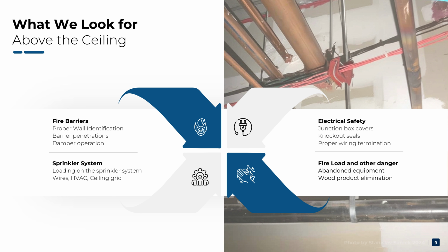Life safety inspections often focus on those hidden spaces because that's where many potential hazards can hide. Like what? Well, we're looking at a combination of things. Electrical and mechanical systems for starters. Electrical safety, exposed wiring, open junction boxes. We check that fire-rated assemblies are intact, that penetrations around pipes or cables are properly sealed and have proper rating identification. Sprinkler system is often found to be used as a support for wires, cables, and other equipment that creates additional stress load on the system, compromising the integrity of the sprinkler system.